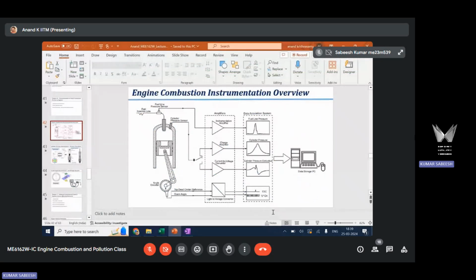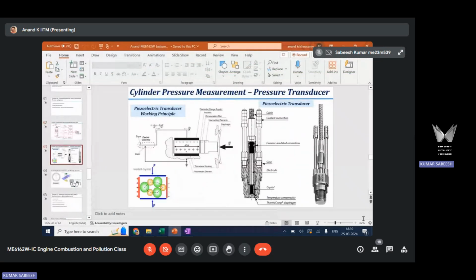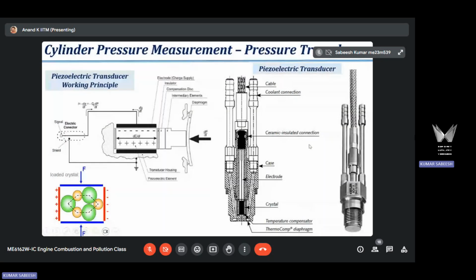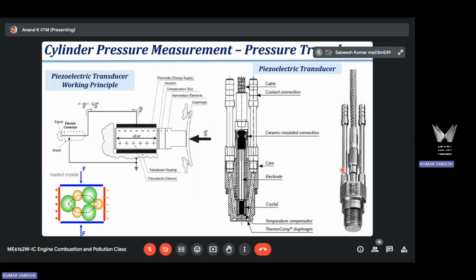And the third thing they will do, you could see here on both sides of the sensor, these are the coolant flow passages. So on both ends, these are coolant flow passages. So you will circulate a cooling medium, generally water, to keep the temperature of the sensing element within the design limit.